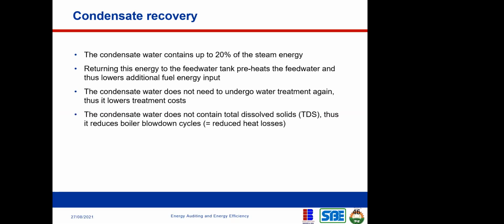So condensate recovery. The condensate water contains up to 20% of the steam energy. That's the water that is now the steam that is now converted to water, and you're removing it through the steam trap. Still contains up to 20% steam energy. Returning this energy to the feed water tank preheats the feed water and thus lowers additional fuel energy input. I've explained all of this. The condensate water does not need to undergo further treatment again, because this does lower its treatment cost. I've also explained this. This is the TDS I talked about.